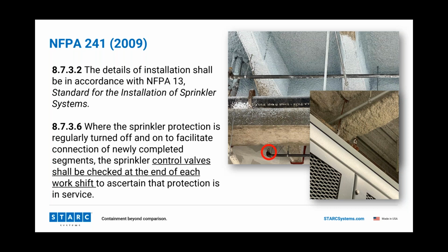So let's look at actually these pictures. There's some sprinklers in these pictures, and there's a few important things here to note. There's a couple of different options. Here you'll see obstructed construction, which is where you actually have structural members below the deck, but there's also unobstructed construction. If you have unobstructed construction, your sprinkler heads have to be within 12 inches of the deck and throughout the entire coverage area. With obstructed construction, you have to be 6 inches below structural members with a max of 22 inches below the deck. So you've got to bring the sprinkler system up to code, is really what I'm saying.